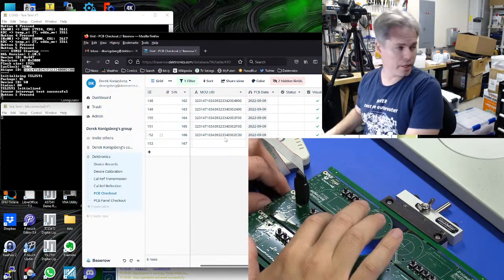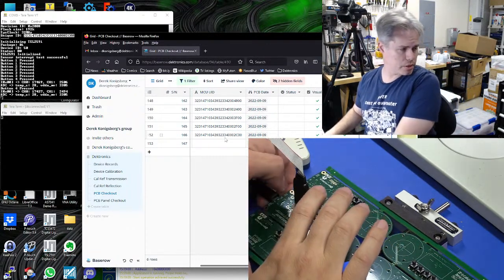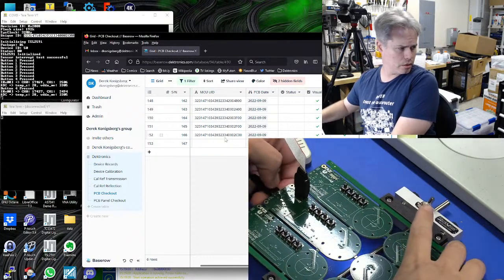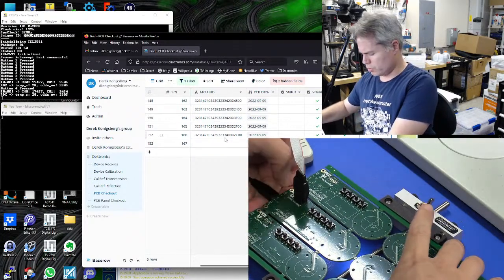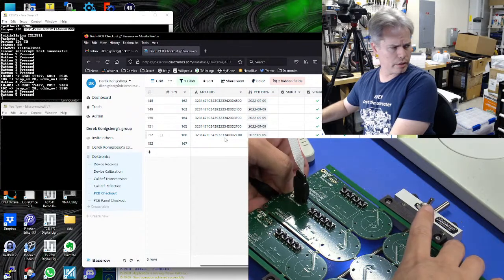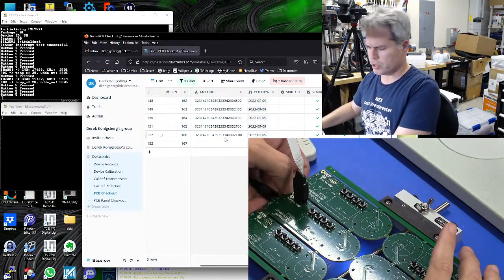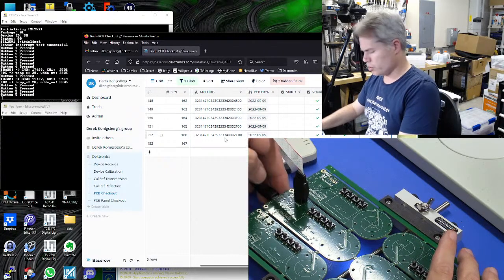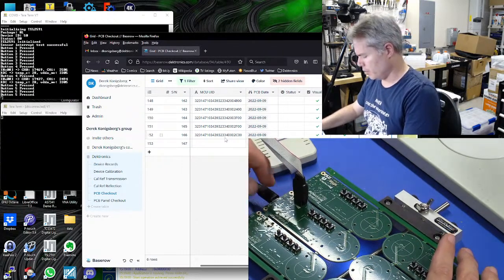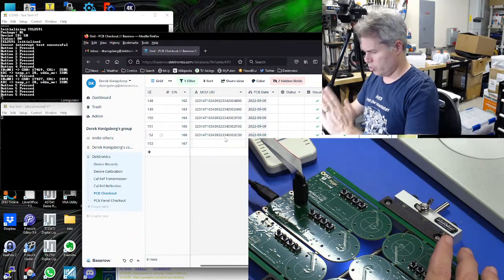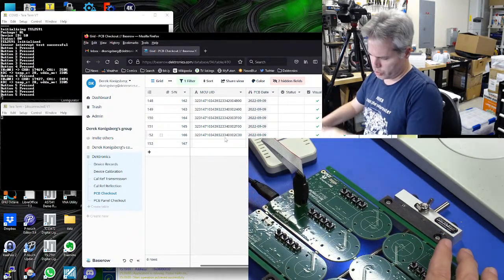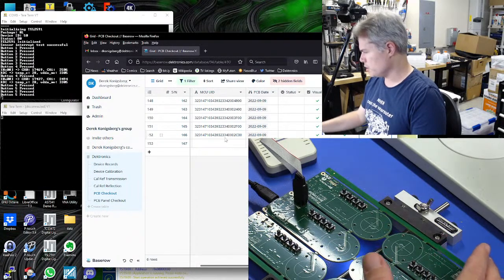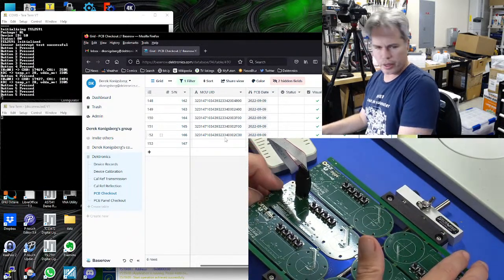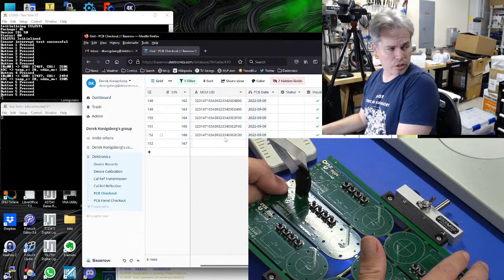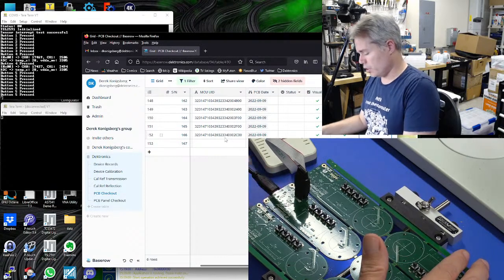I'm going to guess that's another LED issue based on what the power supply is telling me. Okay, this is weird — this has happened on a few boards. The detect switch in the back determines whether the densitometer lid is open or closed, so it knows when to turn the light on. On a few devices it requires excessive travel before it triggers, and this is one of those — I have to press it in all the way and then some before it triggers, which isn't good.